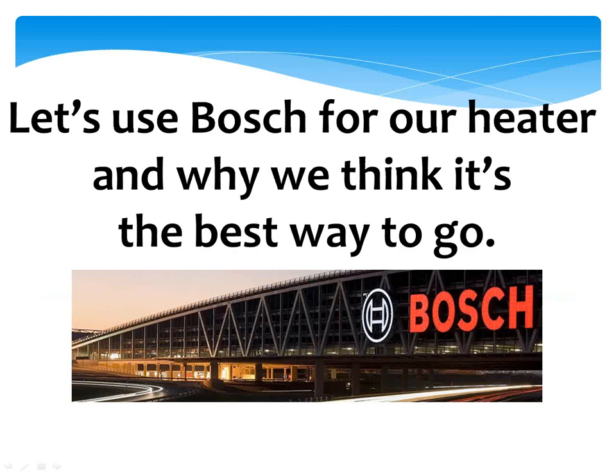So now Bosch has a 225,000 BTU with a 10-to-1 turn down. That's 94% thermal efficiency. We're dealing with a 42-degree temperature rise, and we can do 5.4 gallons per minute. We can set the temperatures on it anywhere from 100 to 140 degrees. We're venting with PVC. Also has the longest warranty out of any of the companies right now, with a 15-year warranty. The small version of it, the one that comes up most commonly, is the 199,000. That's probably one of the most common ones in everybody's brand. Once again, 10-to-1 turn down, 96% thermal efficiency, a 4.7 gallon per minute capacity.